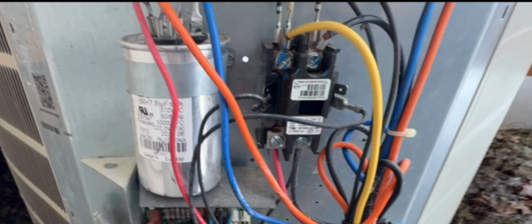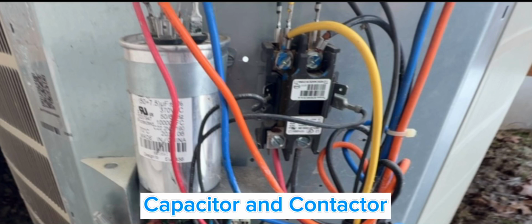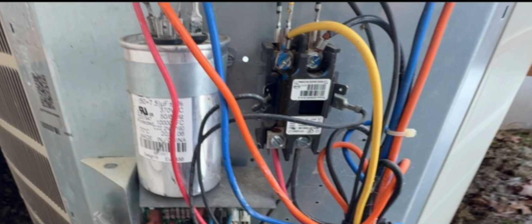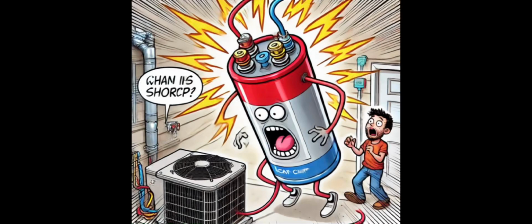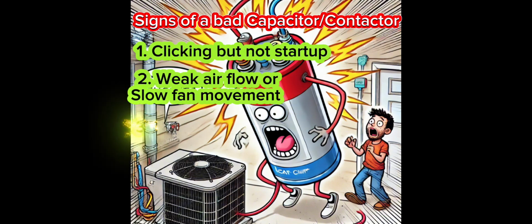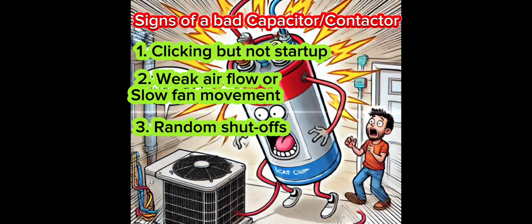Think of these as the starter and relay switch for your heat pump. The capacitor stores and releases electrical energy to start the compressor and fan motors, while the contactor works to provide power flow. If your heat pump makes a clicking sound but will not turn on, or if the fan struggles to start, then these little components could be the culprit.